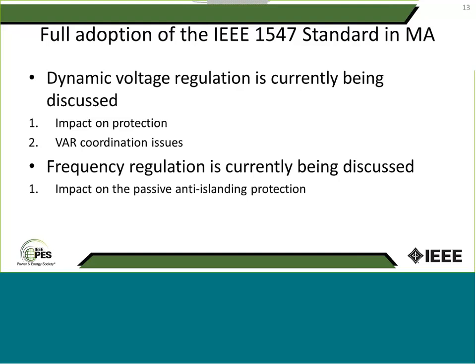So let's start with voltage regulation. For those of you who are not familiar with this concept, the old 1547 2003 version said voltage regulation is not allowed by the DER, so the generators are only mandated to just produce watts and make money for the customer. They can do constant power factor mode, off unity, if the utility requires it and the customer is okay with that. When I say customer, I mean the generator owner. But other than that, there's really no dynamic voltage regulation.